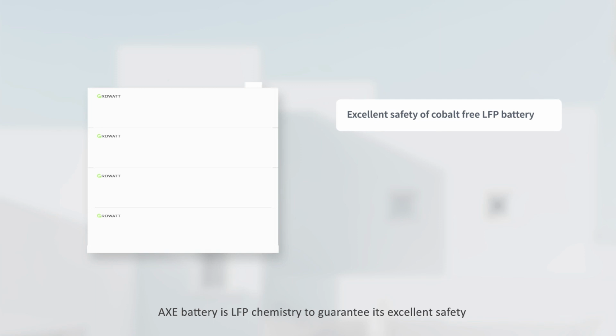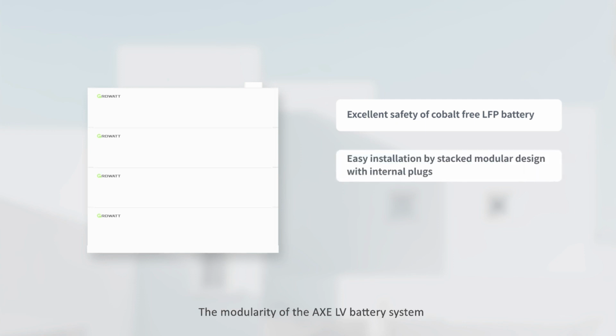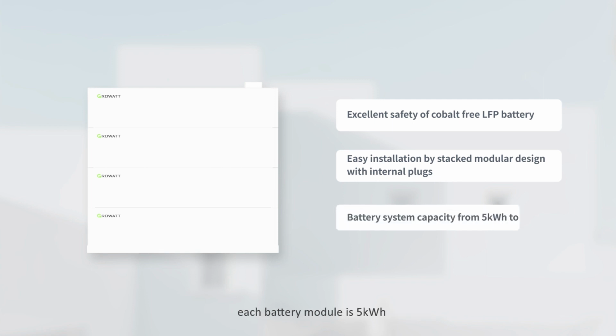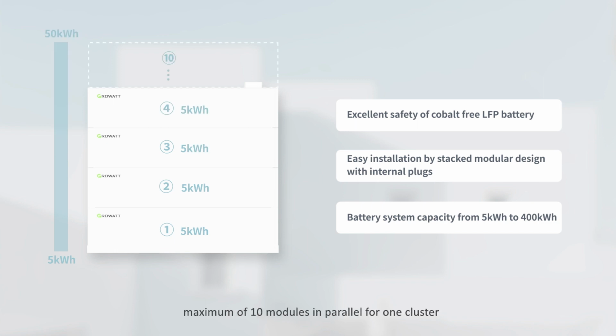The AXE battery is LFP chemistry to guarantee its excellent safety. The modularity of the AXE LV battery system makes it easy to install with plug-in connectors. Each battery module is 5 kWh. A maximum of 10 modules can be in parallel for one cluster. The capacity of a single cluster can reach 50 kWh.